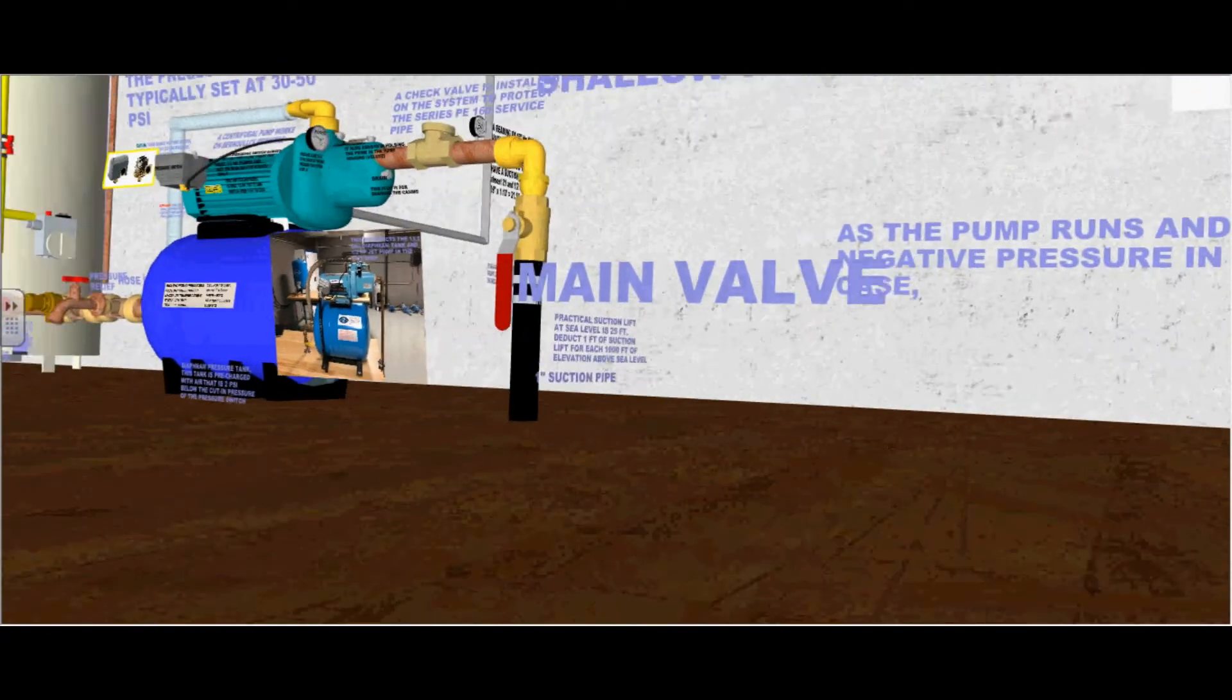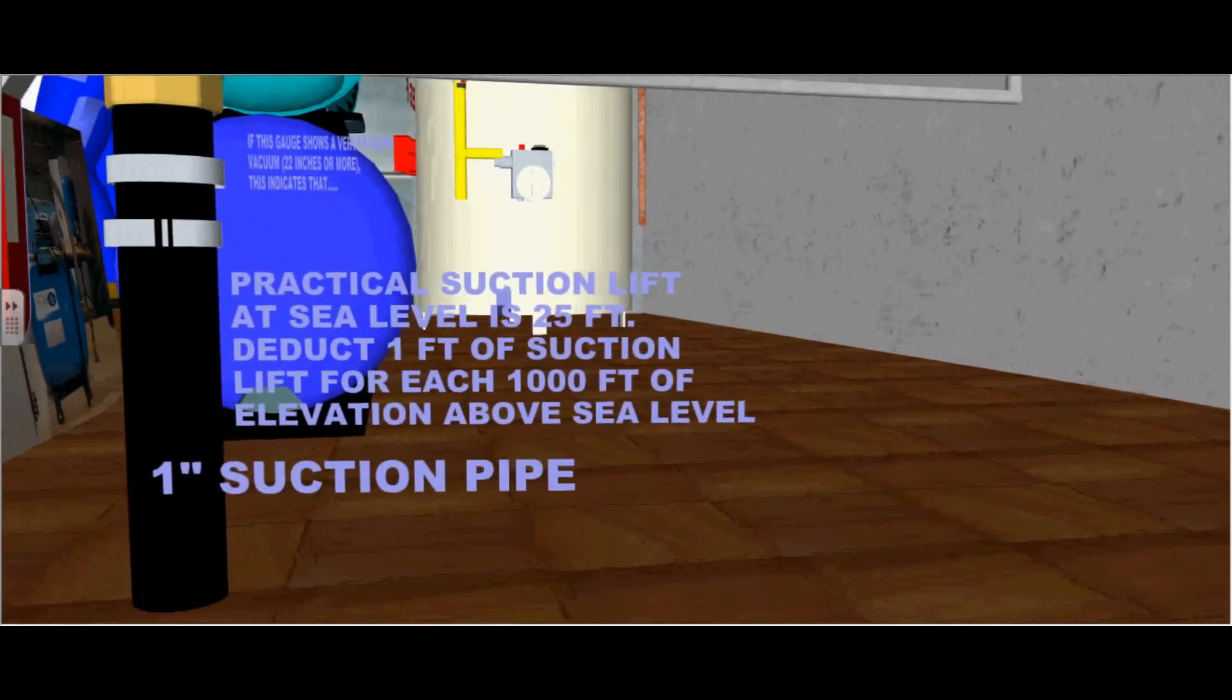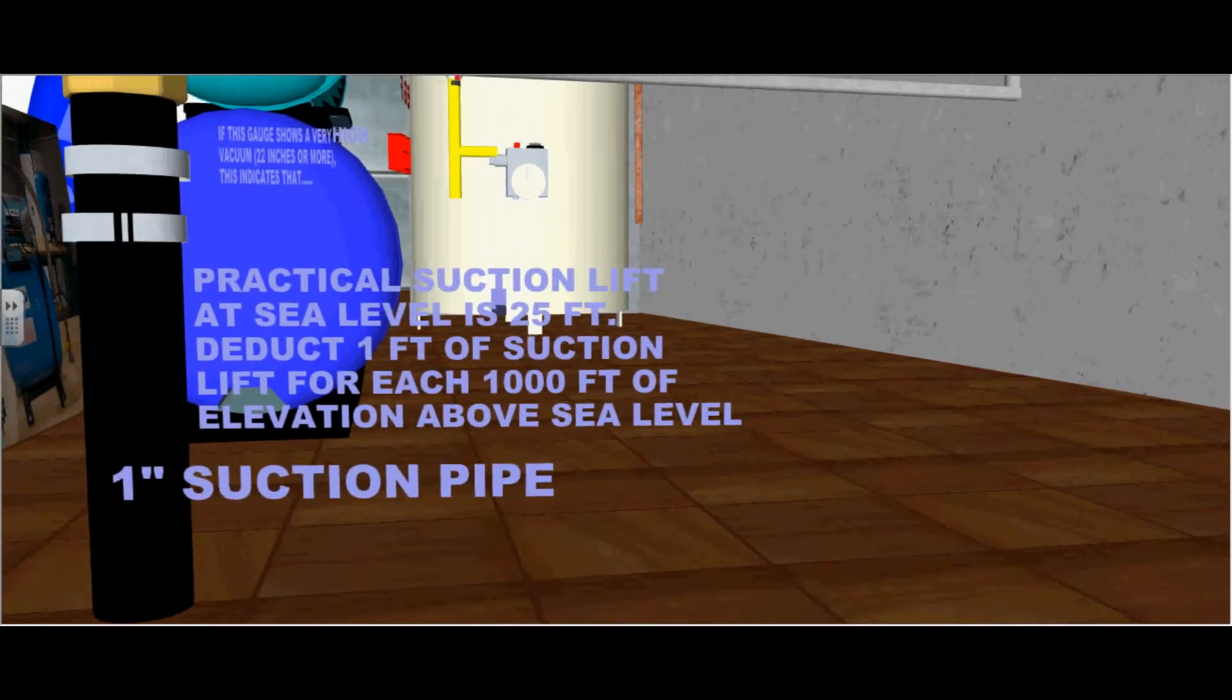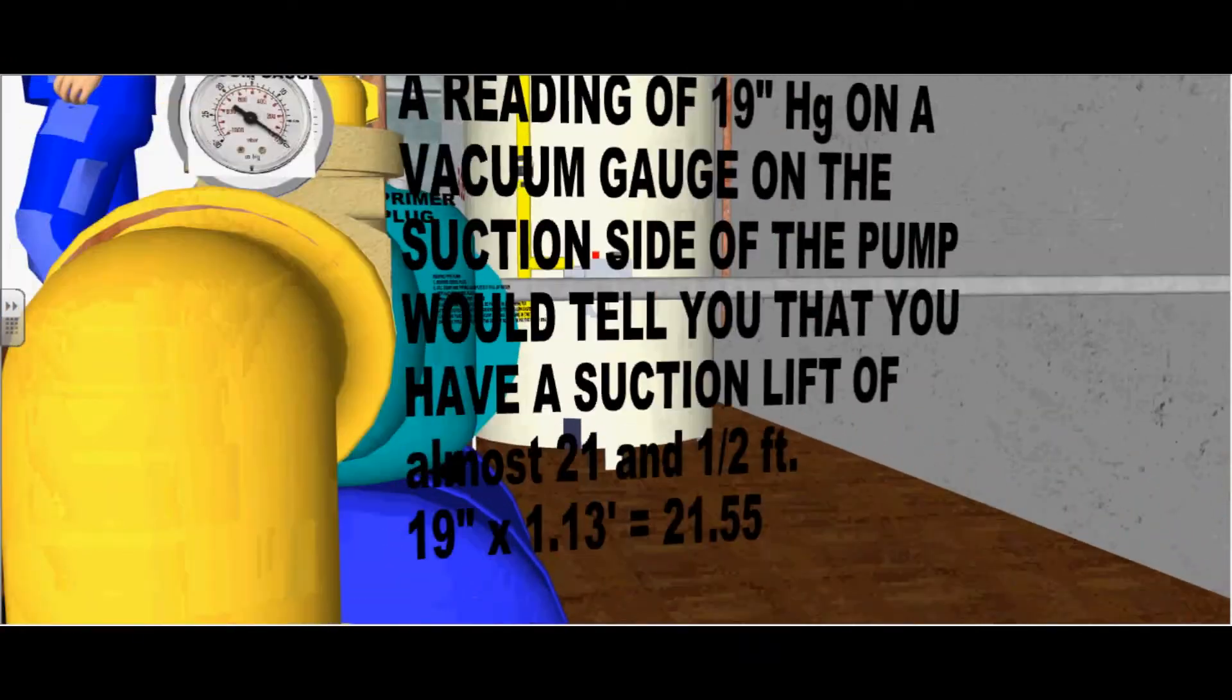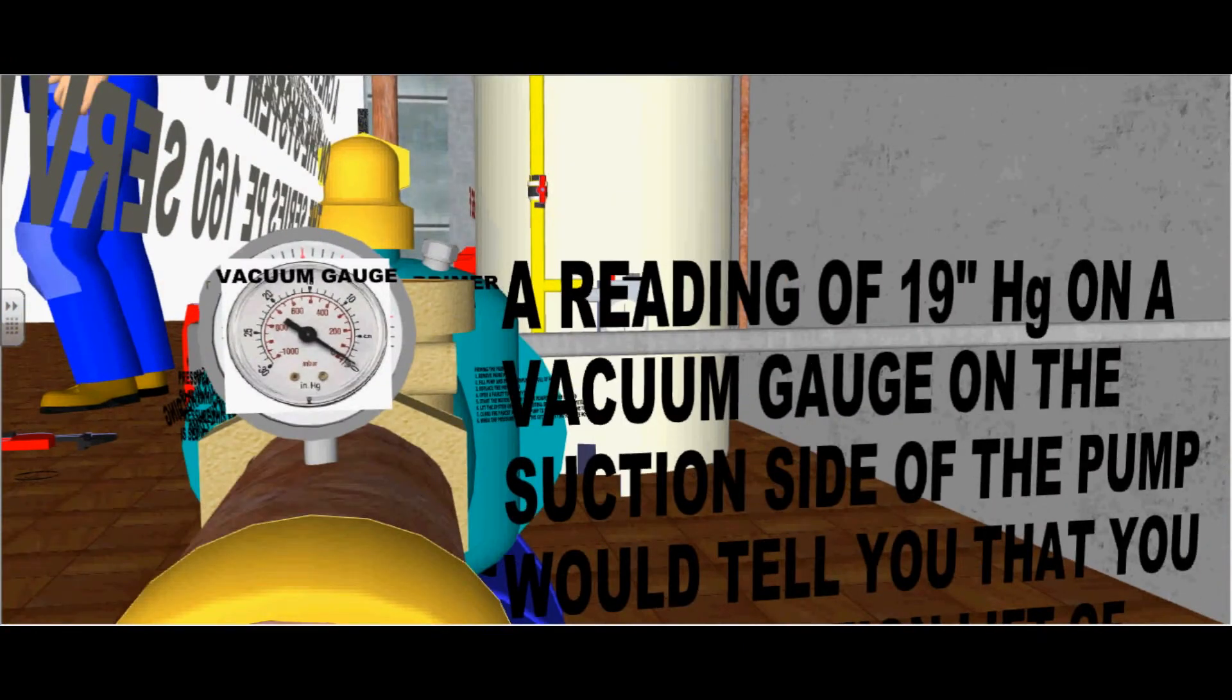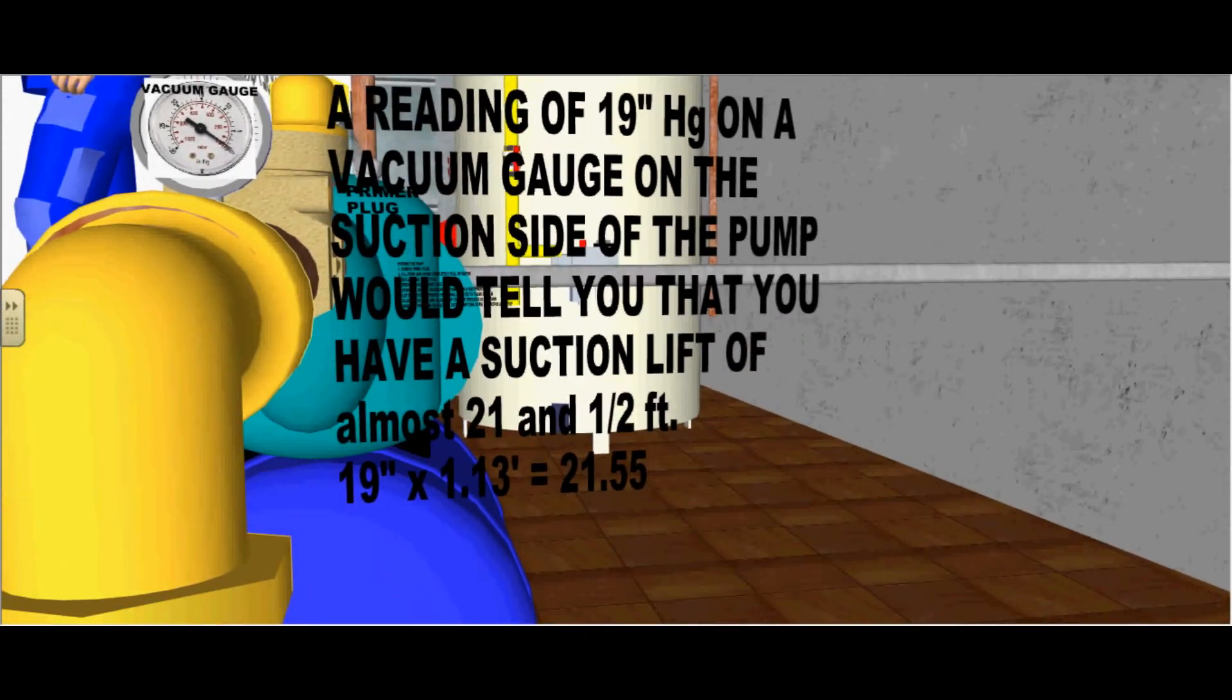This is the 1 inch suction pipe. Practical suction lift at sea level is 25 foot. Deduct 1 foot of suction lift for every 1000 foot of elevation above sea level. A reading of 19 inches mercury on the vacuum gauge on the suction side of the pump will tell you that you have a suction lift of almost 21.5 feet. 19 inches times 1.13 feet equals 21.55 feet.